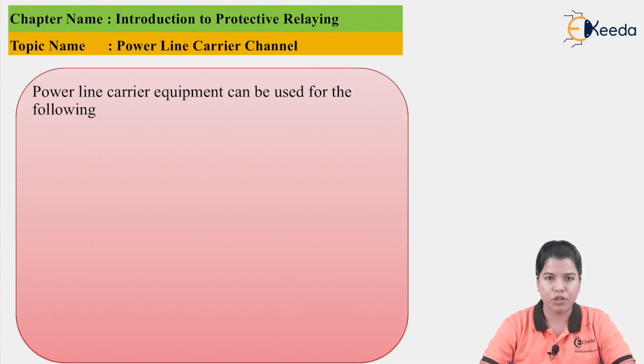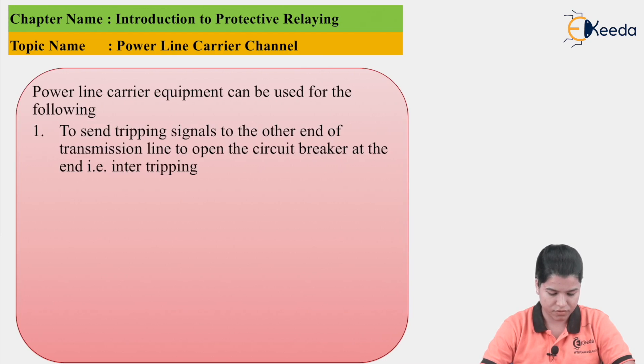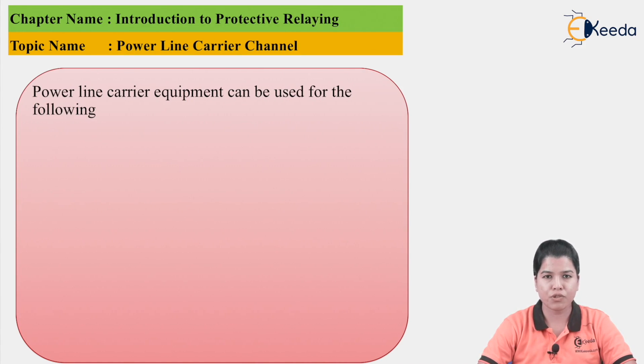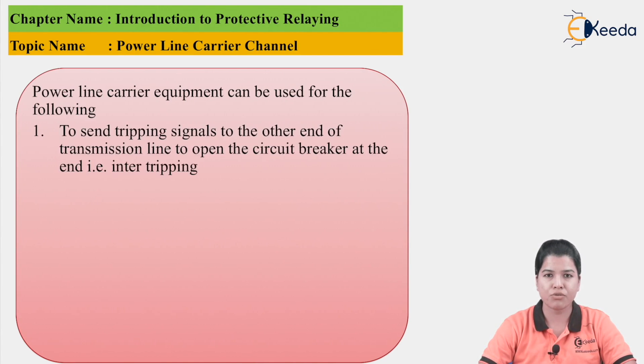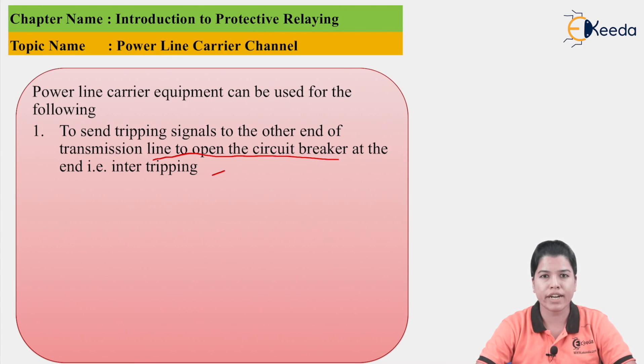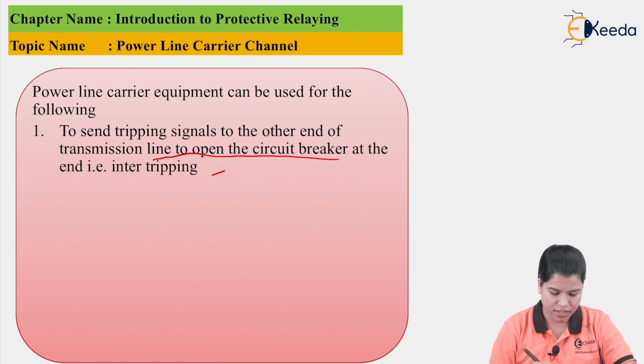The power line carrier equipment can be used for the following functions. First is to send the tripping signal from one end to another end, so as to open the circuit breaker at the other end of the transmission line. This is called inter-tripping. If a fault has occurred, the circuit breaker contacts should open. Usually the signal to open the contacts is sent by the relay, but for fast operation the power line carrier channel can be used to send the signal so that the contacts of the circuit breaker might open.